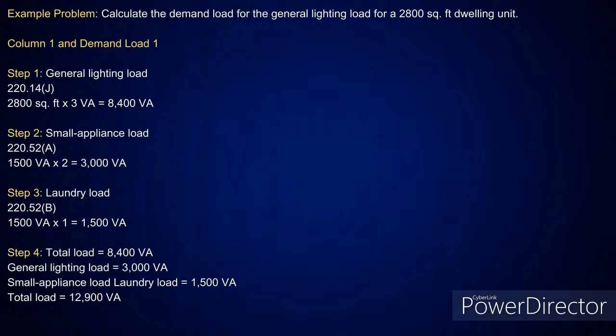Then I go look at 220.52A. You have to have at least 2 small appliance circuits, and they're required to be taken at 1,500 VA each. So that'll give you 3,000 VA, and then you have to have in 220.52B at least 1 laundry circuit there, and it tells you also take it at 1,500 VA. So you just add all of those up, that gives you 12,900 VA. That's about as simple as I can tell you. Just remember, 2 small appliance circuits, you got to have that, and 1 laundry load, and then know the square footage. Take it at 3 VA, total them all up, and you've got your VA.